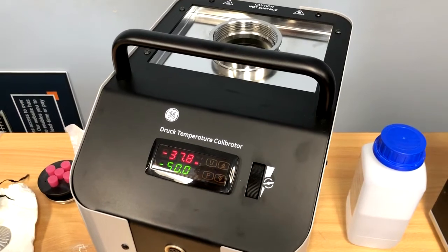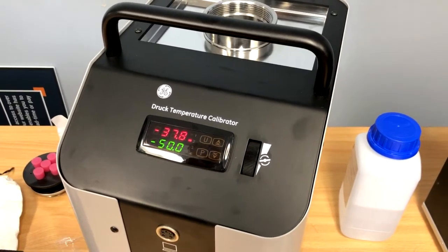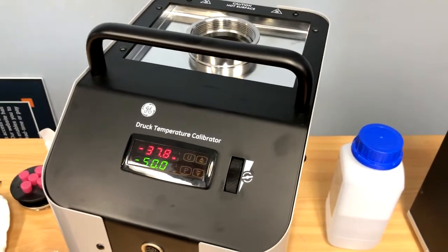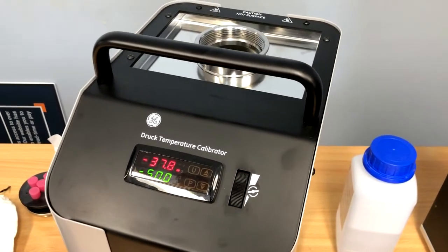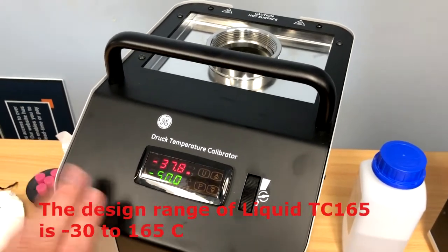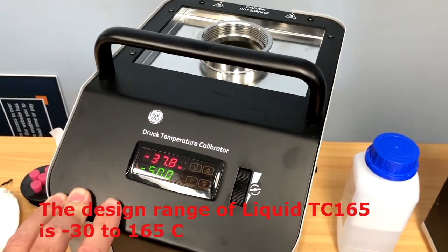We've had the Druck calibrator running for a little while and you can see it gets down to nearly negative 37.8 degrees. We are in an air-conditioned room at the moment. As mentioned, the minimum temperature for this bath is negative 30 degrees.